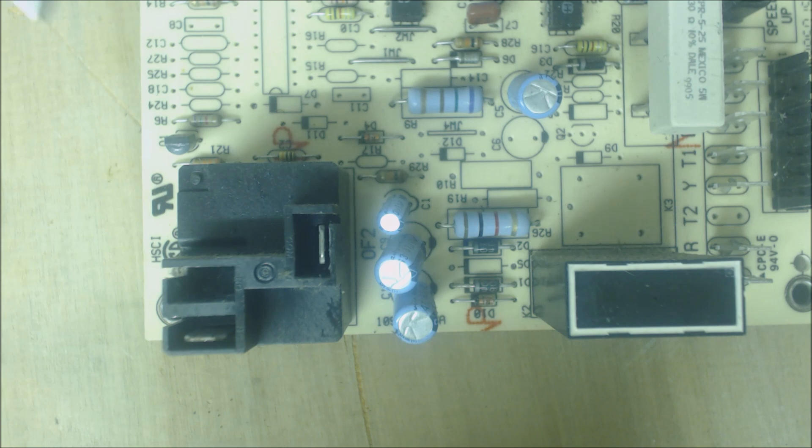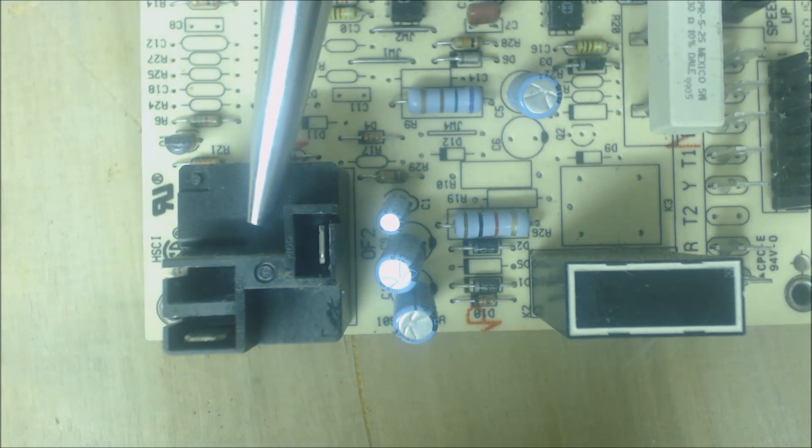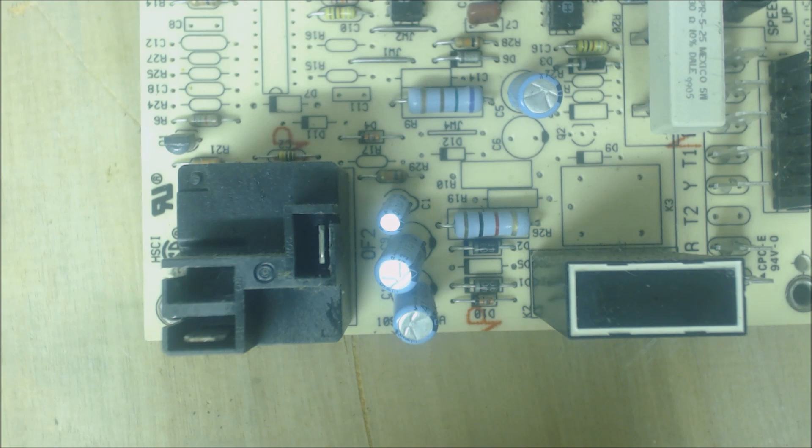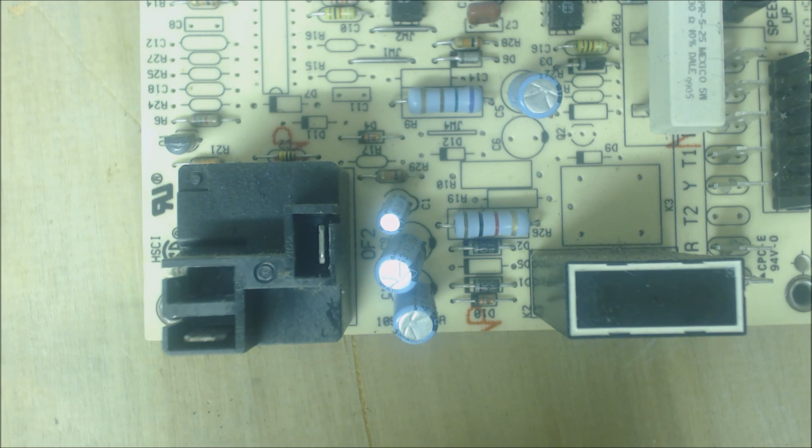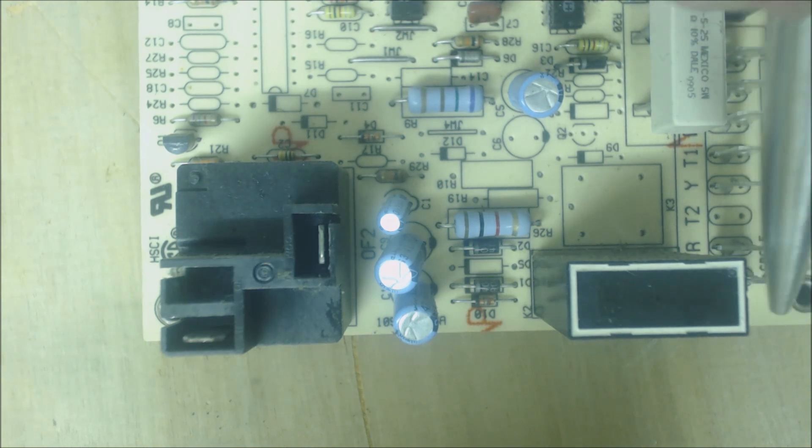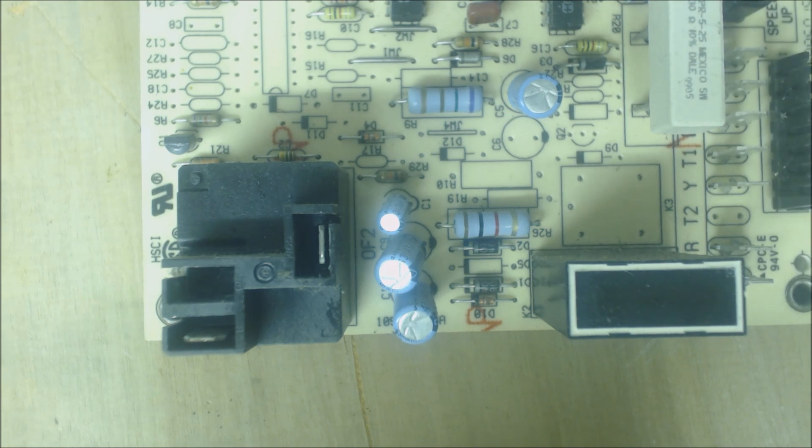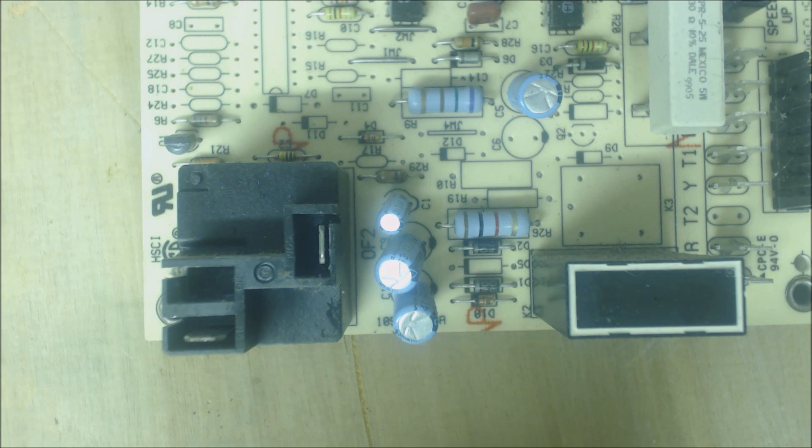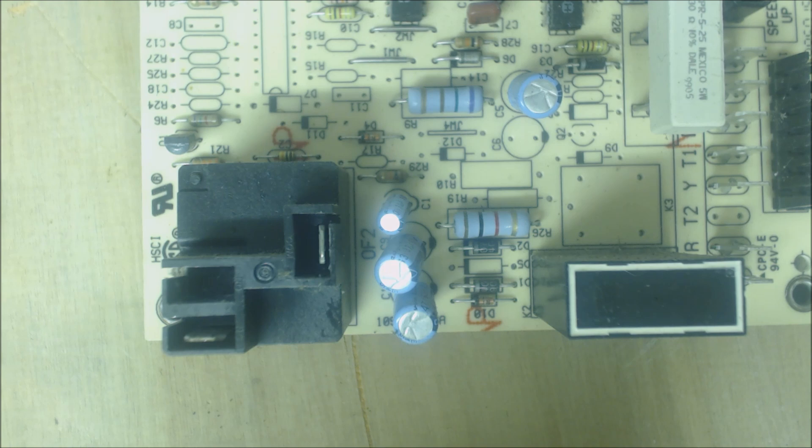So once again, the outdoor fan motor shuts off, W2 sends a signal to the indoor air handler telling electric resistance to turn on, and you have your reversing valve located over here powering the reversing valve and putting it into cooling mode once again because it's not a Rheem or Ruud. It's a Carrier, which means the reversing valve is not powered in heat mode and is powered in cooling mode.